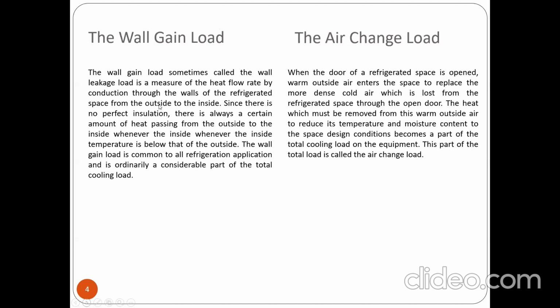Okay. So the wall gain load, sometimes called the wall leakage load, is a measure of the heat flow by conduction through the walls of a refrigerated space from the outside to the inside. Since there is no perfect insulation, there is always a certain amount of heat passing from the outside to the inside whenever the inside temperature is below that of the outside. So the wall gain load is common to all refrigeration applications and is ordinarily a considerable part of the total cooling load.